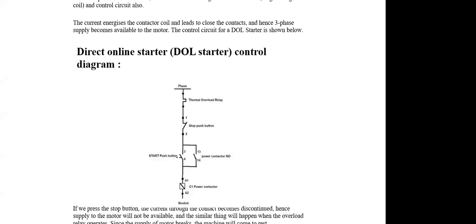So this is how the direct online starter control circuit looks. It is very simple. As you see here, this is the thermal overload. Another important thing: when I'm starting any motor with a direct online starter, in the case of an induction motor, the starting current is 6 times our full load current. That is, I starting is 6 times I full load. That means if my full load ampere is 100 ampere, then my starting current will be 600 ampere. This is point number one.